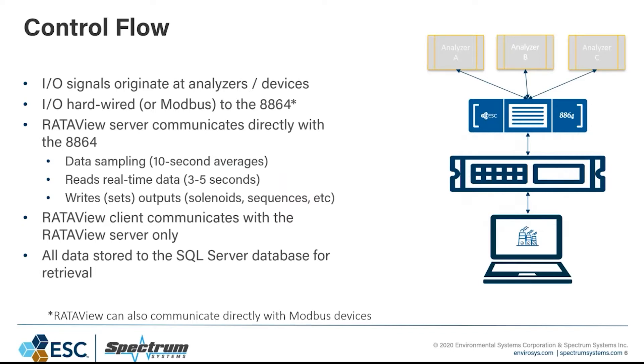I wanted to take a second to go into the control flow of the signals and how those work with the RATAView system. The signals start at the analyzers — emissions data comes from the analyzers down to the 8864. Those are typically hardwired to the 8864 with 4-20mA and some digitals, but we can also do Modbus from the analyzers to the 8864 if you don't want it hardwired.